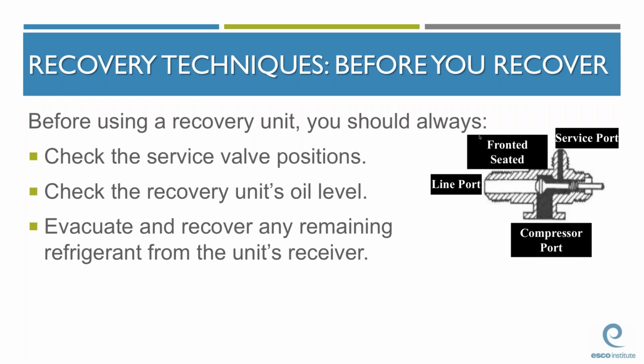We recover refrigerant, we evacuate a system. Some of the EPA terminology talks about evacuating refrigerant, and it's not a term that we typically use. Like I said, we recover refrigerant and we perform evacuation processes on equipment. So we recover refrigerant, we evacuate systems. The EPA does state that we evacuate refrigerant, and that is the EPA regs as written, so we're not allowed to change that. So you might definitely want to alert your students if they see a question on the EPA test that talks about evacuating refrigerant, and what they're actually talking about is recovery.